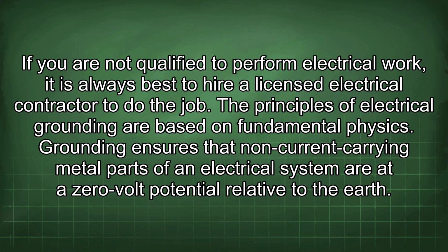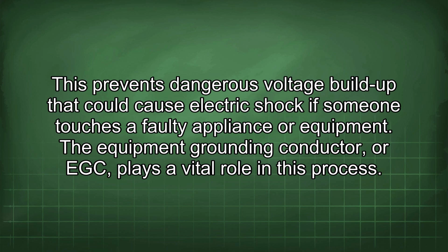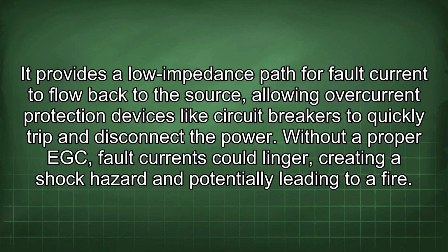Grounding ensures that non-current carrying metal parts of an electrical system are at a 0-volt potential relative to the earth. This prevents dangerous voltage build-up that could cause electric shock if someone touches a faulty appliance or equipment. The equipment grounding conductor, or EGC, plays a vital role in this process. It provides a low impedance path for fault current to flow back to the source, allowing overcurrent protection devices like circuit breakers to quickly trip and disconnect the power. Without a proper EGC, fault currents could linger, creating a shock hazard and potentially leading to a fire.